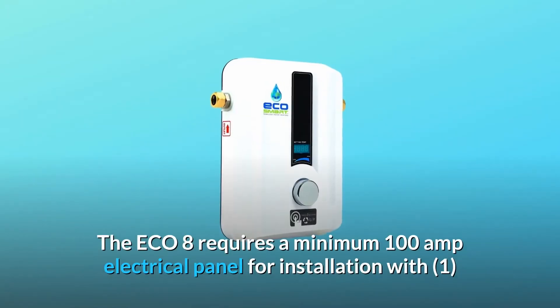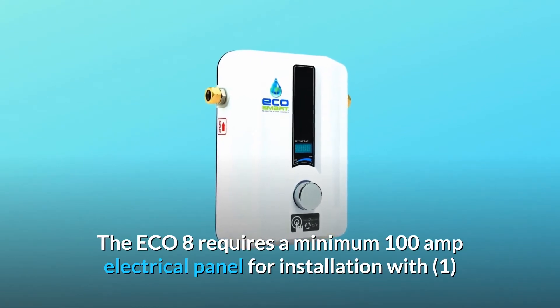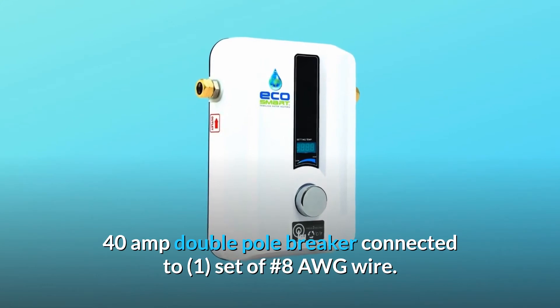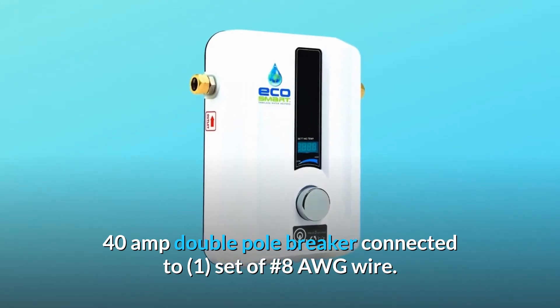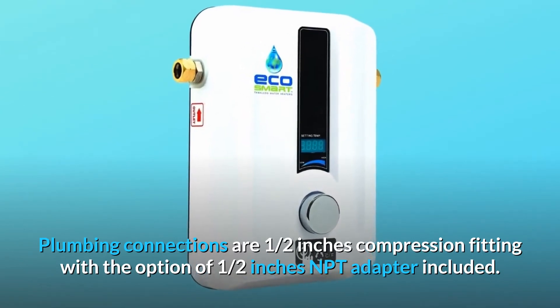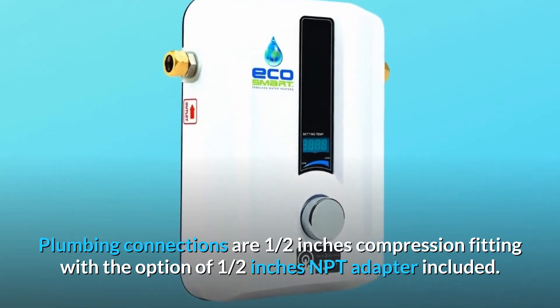The ECO 8 requires a minimum 100-amp electrical panel for installation, with one 40-amp double-pole breaker connected to one set of #8 AWG wire. Plumbing connections are half-inch compression fitting with the option of half-inch NPT adapter included.